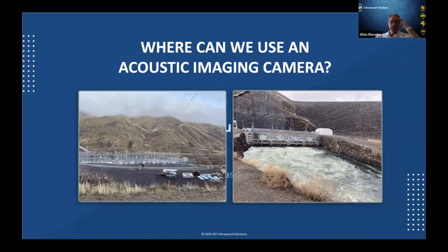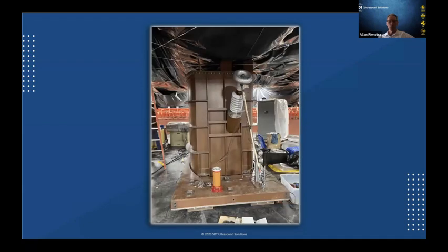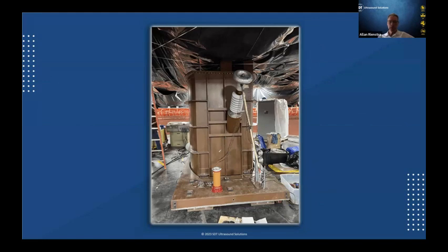So I want to talk about a really interesting application we use, and this is a hydroelectric dam in Western United States. One of my customers in Erie, Pennsylvania, what he does for a living is he goes around and tests different facilities for electrical integrity. He was called in. They were doing a big rewind, and he was called in to do some testing and commissioning before they put this back into service. So here's a high pot that he used to do some of his testing.